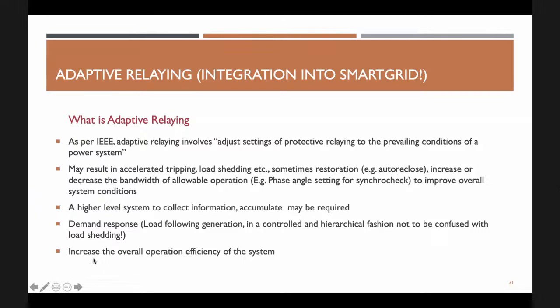Ultimately, what we need to achieve is to increase the overall operation efficiency of the system. One thing we should also remember is that in the good old days of the EHV system, the protection engineer's role was very, very critical, because if he didn't do his job well, a blackout was more or less certain. We need to make sure that protection operates in a maximum of maybe 2 cycles, and the breaker should trip in 3-4 cycles maximum, or 2 cycles typically. So less than 100 milliseconds to open the fault, and give another 100 milliseconds or so for the fault to recover. Maximum 200 milliseconds is the time we are looking at.